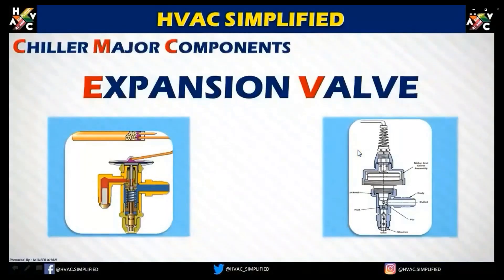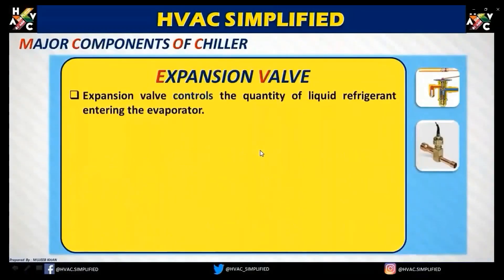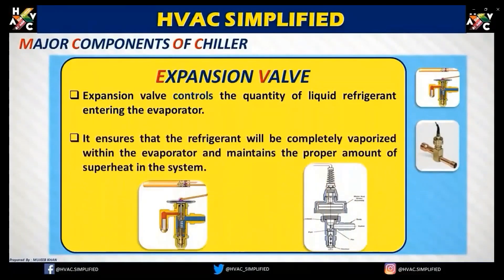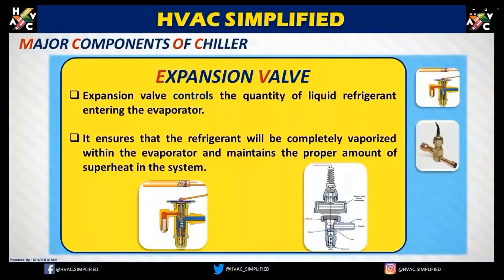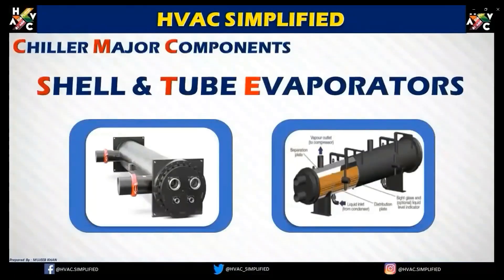Now we will see the expansion valve. The expansion valve controls the quantity of liquid refrigerant entering the evaporator. It ensures the refrigerant will be completely vaporized within the evaporator and maintains a proper amount of superheat in the system. The expansion valve is one of the four major components of the refrigeration cycle.